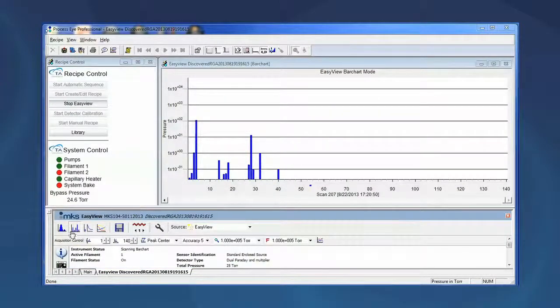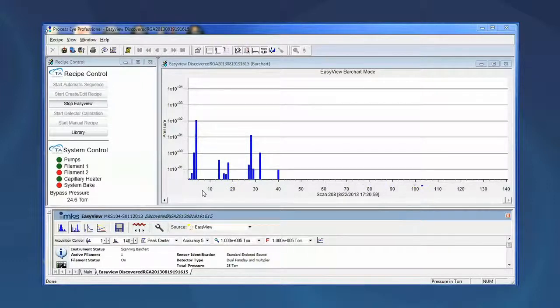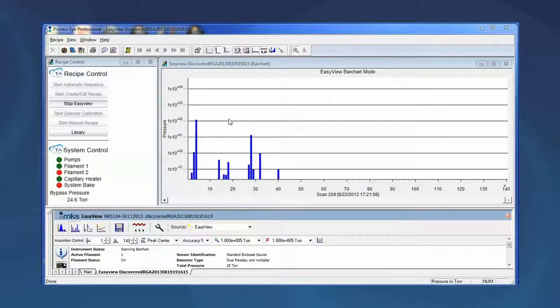The bar chart mode is accessed by clicking on this icon. It gives an updated scan of the ions being detected by the mass spectrometer. The furnace is in the closed position now and these are the ions that would be in the background of your mass spectrum as you scan your sample. Since background subtraction is not done with this instrument, it is important to know which ions exist in the background and be able to distinguish them from your sample ions.